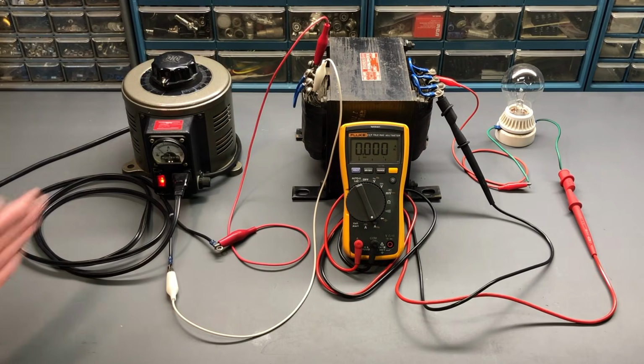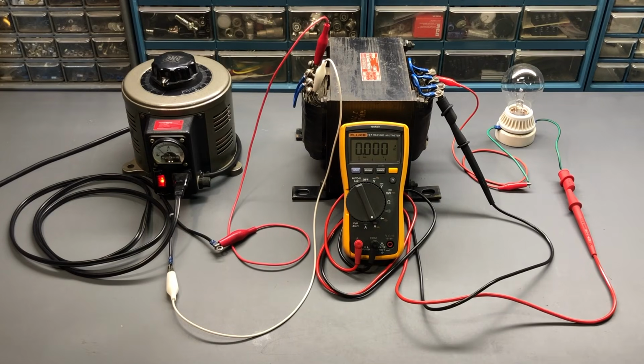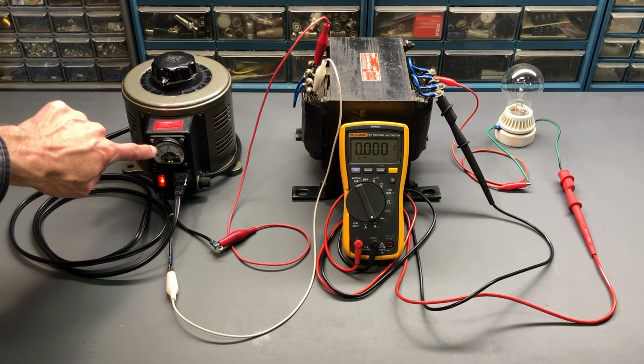It's just the current that flows under no load. You would see some indication, again very similar to the current that we saw flowing through the 25-watt bulb when it was placed between the Variac and the isolation transformer. Well, in this case, this meter would be showing that current flow.